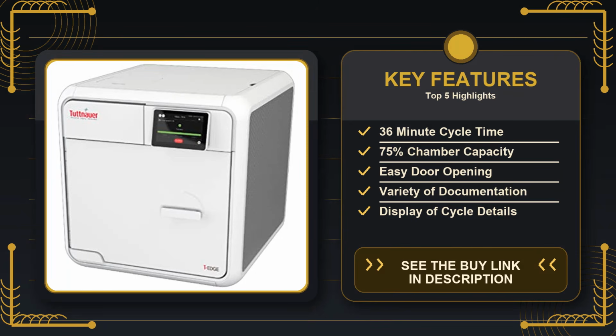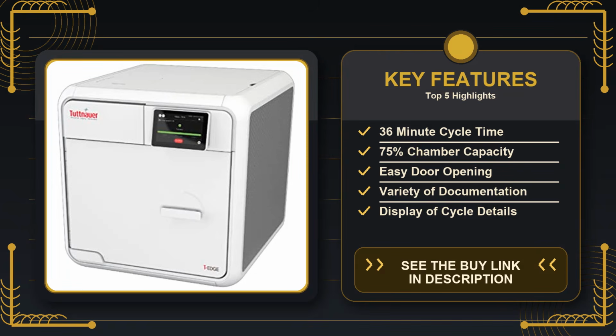The real-world day-to-day experience pivots around that 36-minute wrapped instrument cycle. For many small practices, the biggest pain point is the drying phase. A partially dried set of instruments can lead to rust or, worse, patient infection risk. The EDGE10S claims a complete cycle including drying within that 36-minute window. In a typical morning schedule, you could run a load just before the first patient, have everything ready for the second, and still have time to fit in a quick second load before lunch.